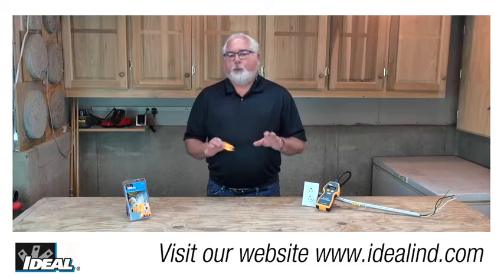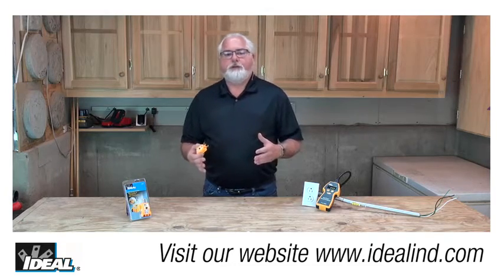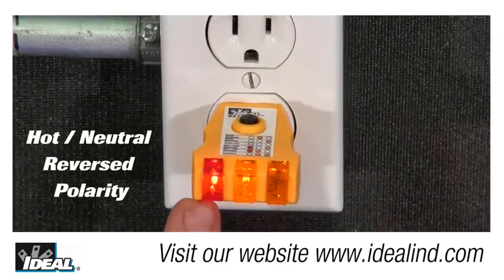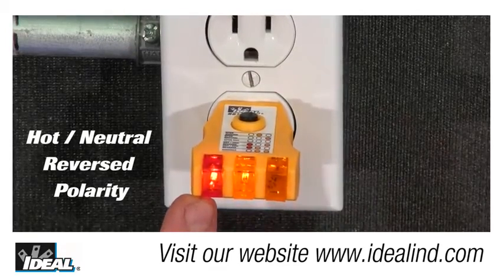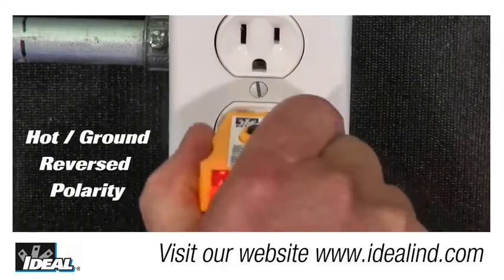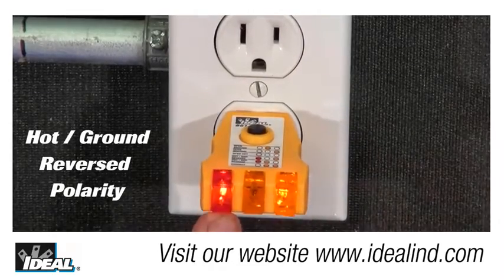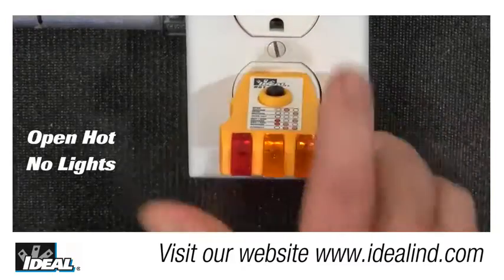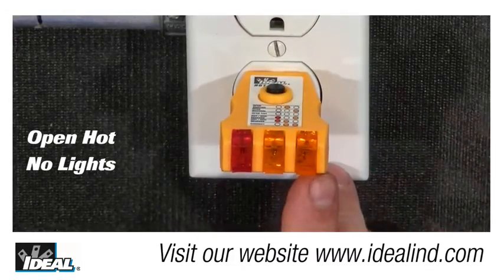Now, reverse polarity, or a reversal of the hot and neutral conductors, is indicated by just the left red bulb and the middle bulb lit on the tester. When the receptacle tester sees a hot and ground conductor reverse, the left red bulb and the far right bulb are lit up.